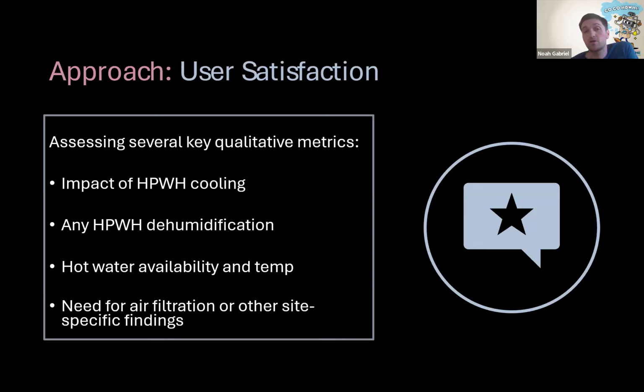A couple things to note though: especially for those integrated units like the CHP 120, you do want enough cubic air volume, about 3,200 cubic feet - a pretty decent sized room. Otherwise you can overly cool off the space, which triggers more use of the electric resistance elements and decreases the efficiency of the system. I did speak with someone with a commercial kitchen who ran into that issue, but luckily they were able to do some ducting and bring in more airflow, and the performance was perfectly solid. Just a good thing to keep in mind.